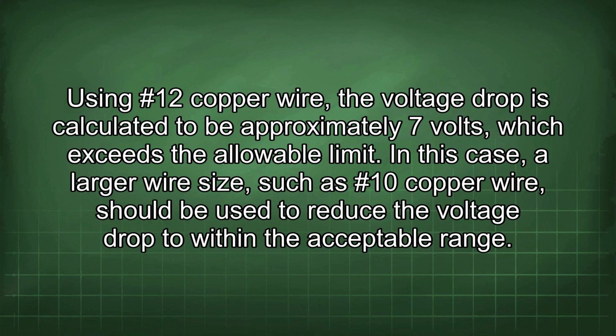Using #12 copper wire, the voltage drop is calculated to be approximately 7 volts, which exceeds the allowable limit. In this case, a larger wire size, such as #10 copper wire, should be used to reduce the voltage drop to within the acceptable range.